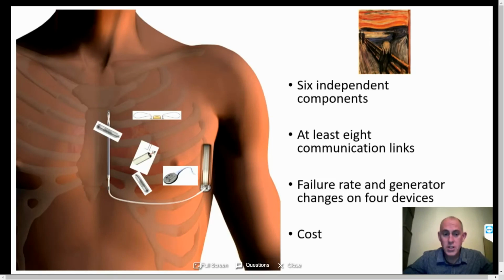So the SICD is probably not a lot more expensive than a standard transvenous ICD, but the Micra is somewhere between 5 and 10 times the cost of a standard bradycardia pacemaker, and the LV endocardial system has two separate components to it, each of which costs about the same as a standard CRTP. So if you put all of those together, compared to the cost of a CRTD, it's going to be at least four times the cost.